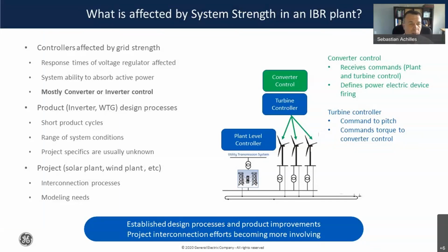So generally speaking, what is really affected when we talk about IBR stability? It's mostly about the converter control. There are some other aspects, but they're typically easier to resolve. There are already practices in place by vendors to deal with low system strength, but you can see there are limitations to this approach too, because of how the product design cycle works.